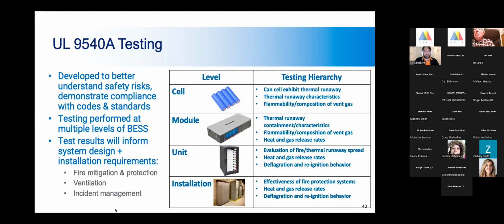Here we are back at 9540A. This is also called large-scale fire testing. In the fire code, you will see it primarily referred to as large-scale fire testing. Anytime you see the words large-scale fire testing in relation to energy storage, we are talking about UL 9540A testing. We can use those terms interchangeably.